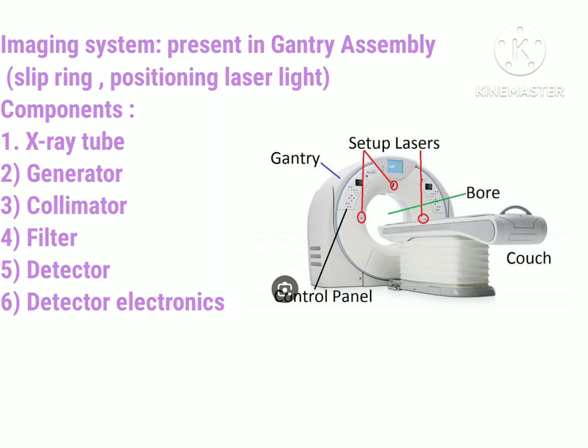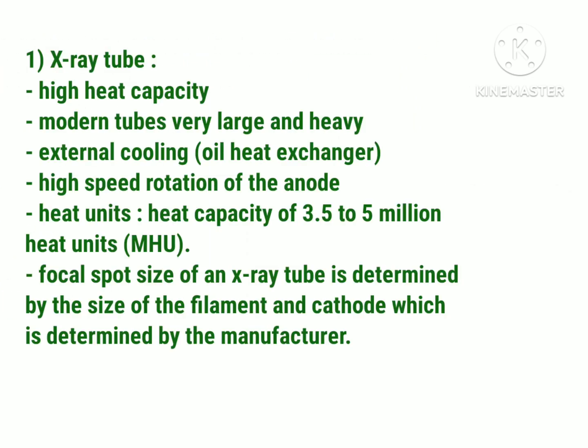The first component of the gantry is the x-ray tube from which x-rays are produced. The x-ray tube has a high heat capacity; it is made up of modern tubes which are very large and heavy. It has external cooling with an oil heat exchanger, and high speed rotation of the anode is present. Heat units are 3.5 to 5 million heat units. The focal spot size of the x-ray tube is determined by the size of the filament and cathode, which is determined by the manufacturer.